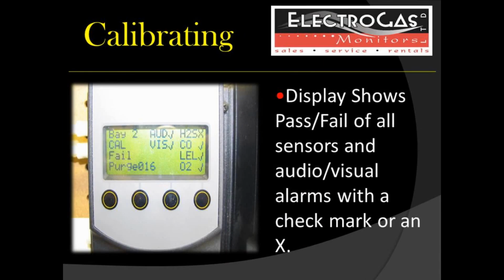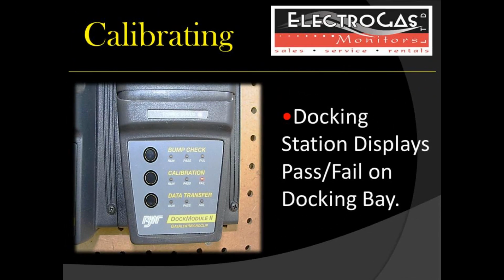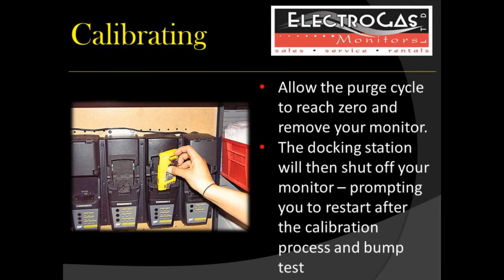Once calibration is complete, the display will show a pass or fail of all sensors and audio-visual alarms with a check mark or an X next to them. The docking module itself will also display a pass or fail with either a green or a red light. Again, allow the purge cycle to reach 0. Once the purge cycle is complete, the docking station will shut off your monitor, prompting you to restart your monitor and perform a bump test.